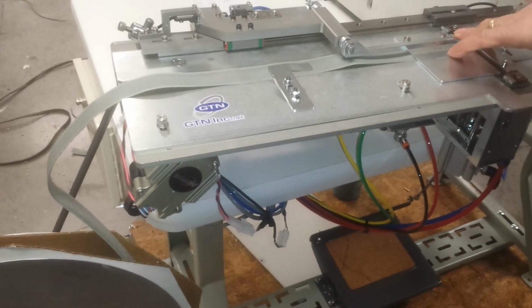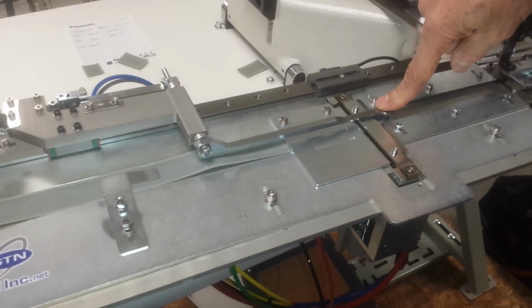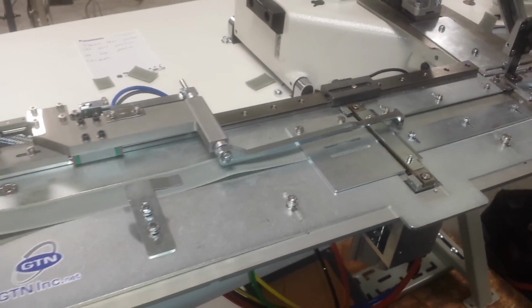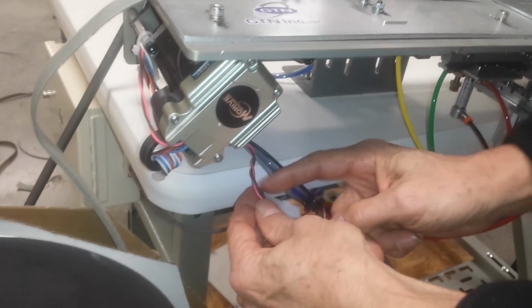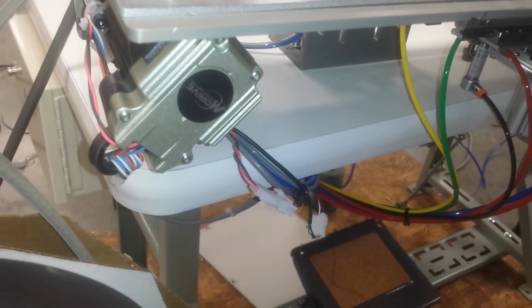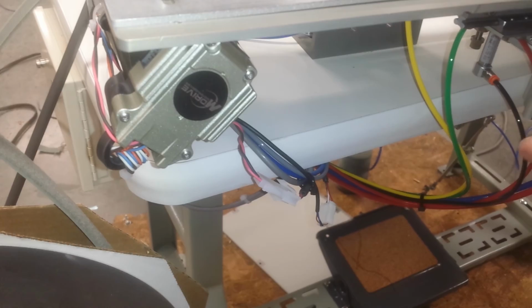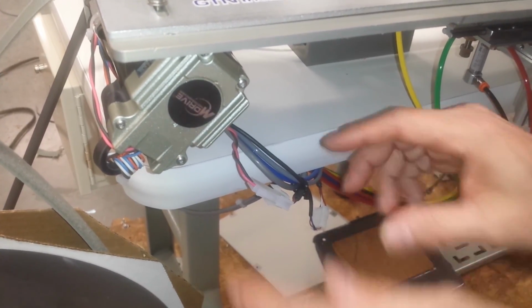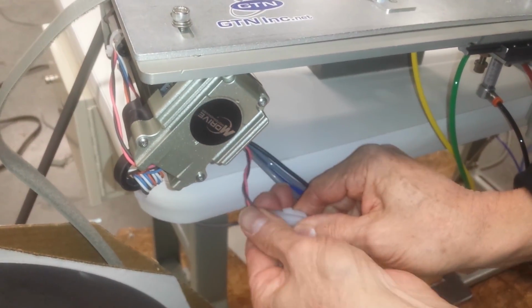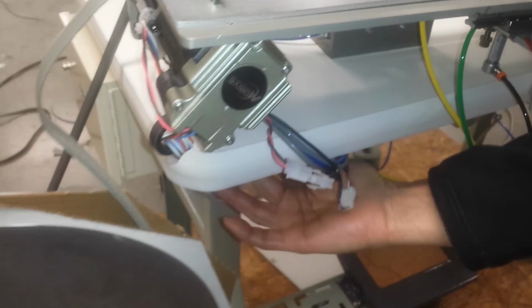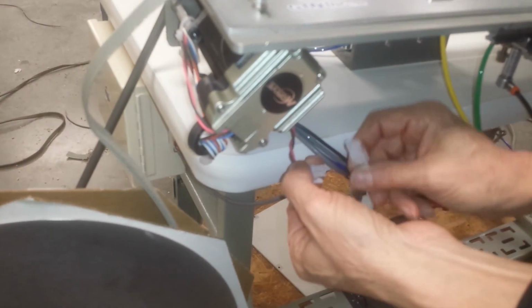Okay, we established this position is where we want it, at 6 millimeters. At this point, unhook the 2 wires at the motor with the power off. Never do this with power on, you'll burn the motor up right away. When the power's off, you can unhook the 2-prong connector — there's a 4-prong and a 2-prong, the 2-prong is the one you want to unhook. Now you can power back up.